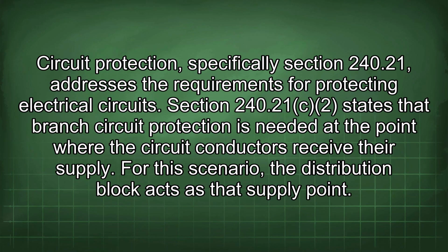Circuit protection, specifically Section 240.21, addresses the requirements for protecting electrical circuits. Section 240.21 states that branch circuit protection is needed at the point where the circuit conductors receive their supply. For this scenario, the distribution block acts as that supply point.